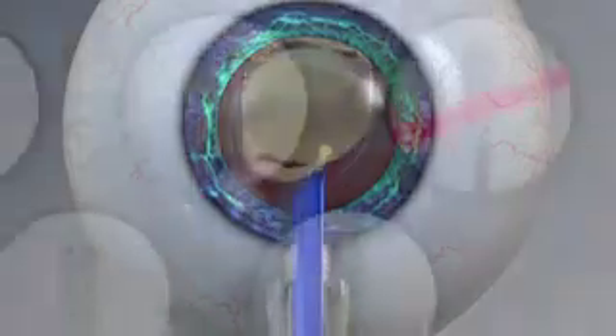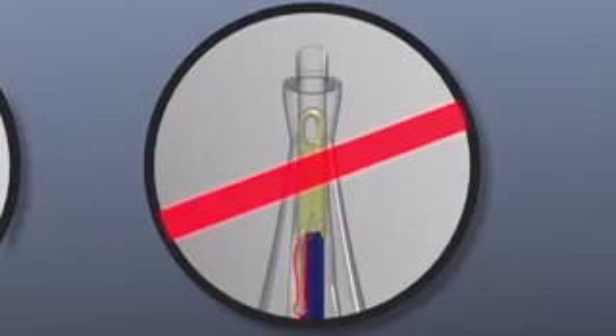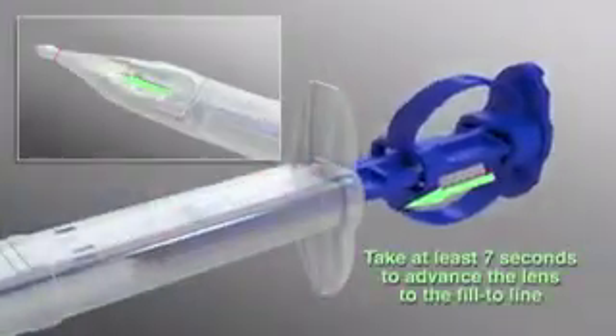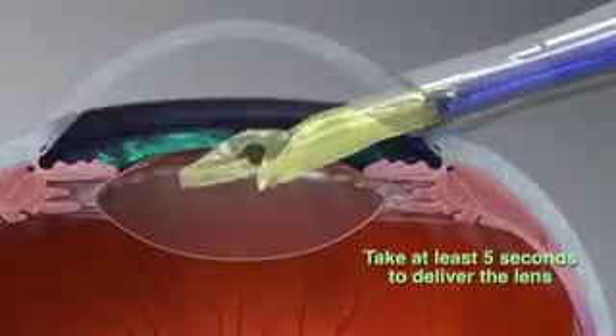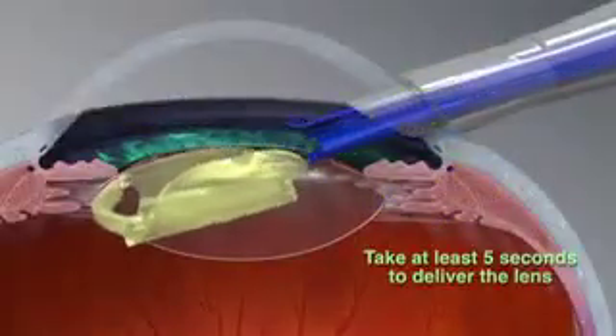This straight trailing haptic configuration cannot be delivered. Do not proceed with this lens implantation. In this rare case, contact your Alcon representative. Finally, please remember, take at least 7 seconds to advance the lens to the fill-to line, and take at least 5 seconds to deliver the lens to avoid lens damage.